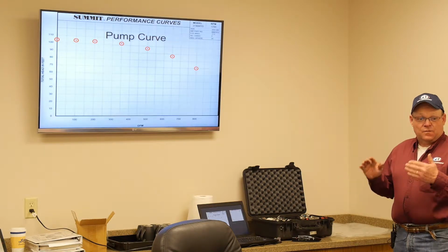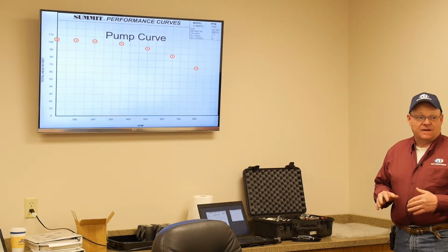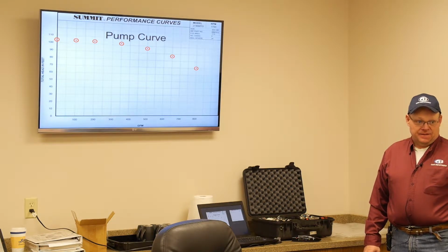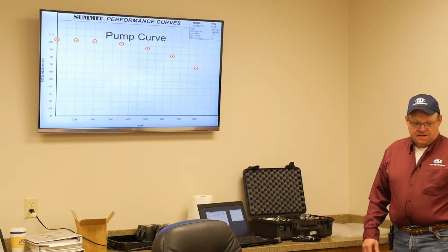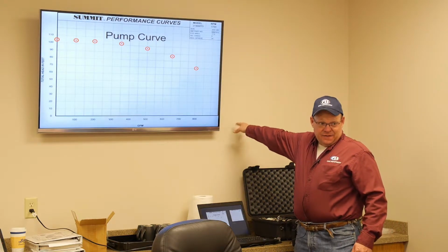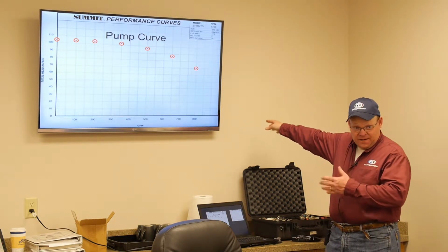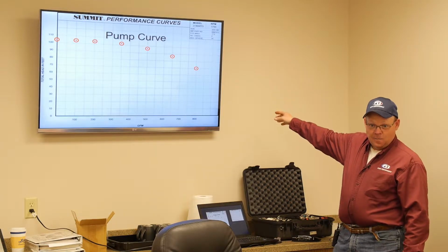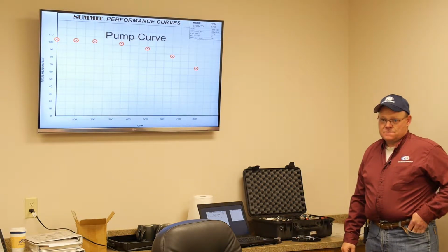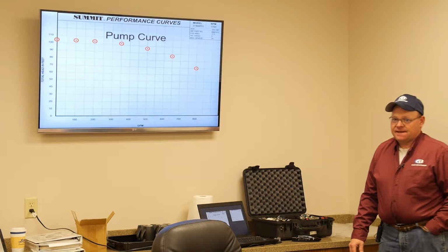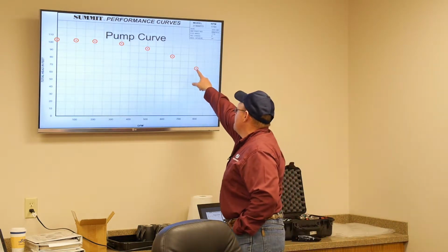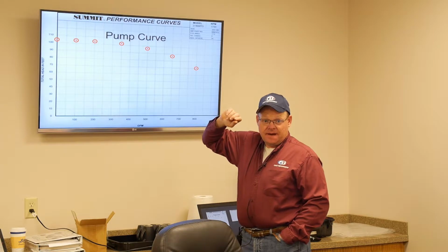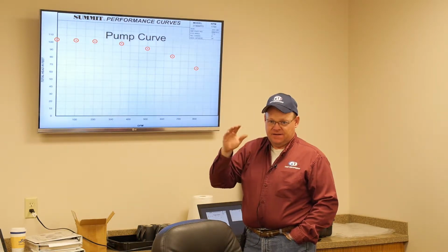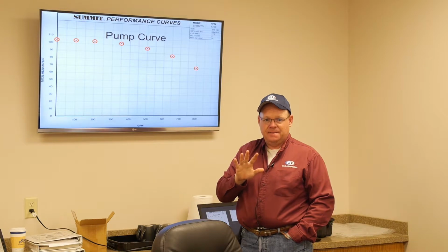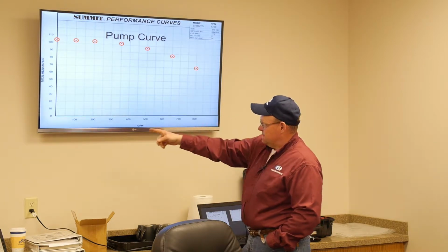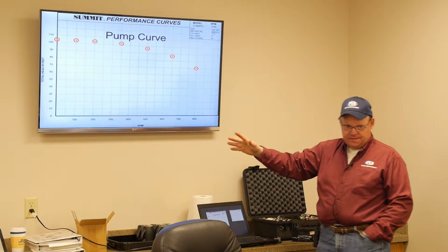Okay? Now if you have virtually no pressure, say you only had 30 pounds of pressure, what's going to happen to the pump? It's going to be way at the bottom. Way over here somewhere, out here in left field. And I'll show you that's not a good place to be either. Now, when you say the 15 pounds difference, where's the 15 pounds again? You're talking line pressure? Yeah, it's system pressure. If you change the system by 15 pounds, you're going to quadruple the flow or cut it.